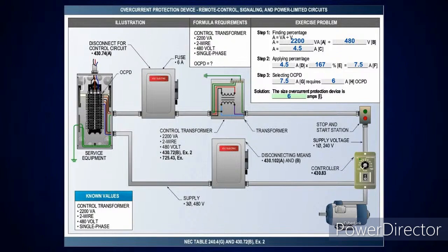It's going to tell you it's less than 9 amps, but more than 2 amps, so take it at 167%. That'll give me 7.5. Now you'll notice looking in the table there, there's no superscript 1 there. Since there's not a superscript 1 on that percentage, that means I'm going to drop down to the next standard size, which is a 6 amp overcurrent protection device.